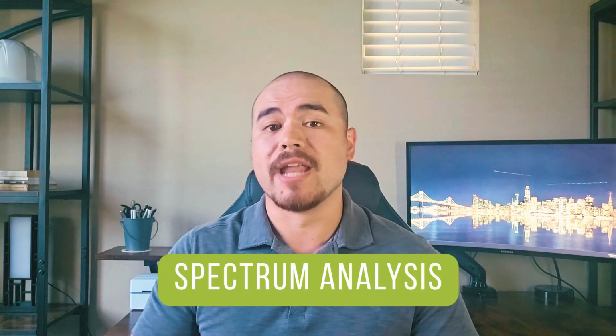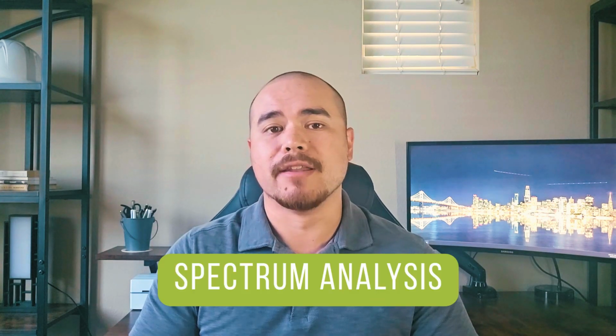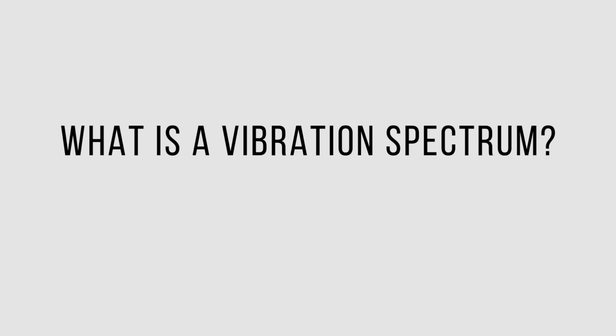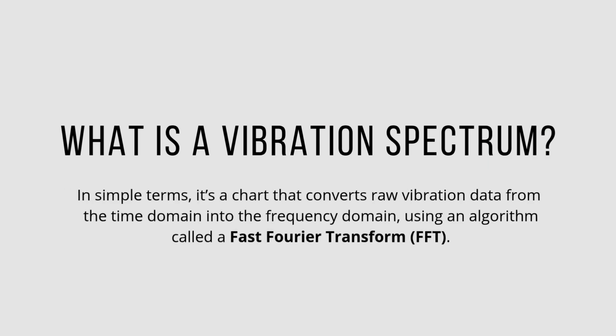Today, we're exploring another essential tool in the vibration analyst's toolbox, spectrum analysis. Let's dive in. So what is a vibration spectrum? In simple terms, it's a chart that converts raw vibration data from the time domain into the frequency domain, using an algorithm called a fast Fourier transform, or FFT. It might sound technical, but here's why it matters.